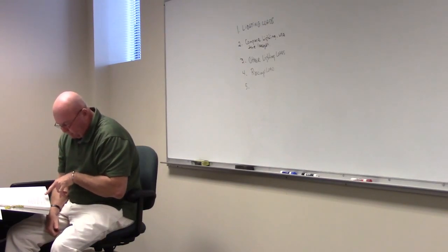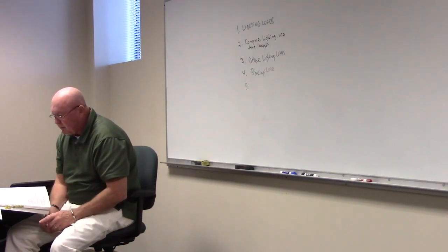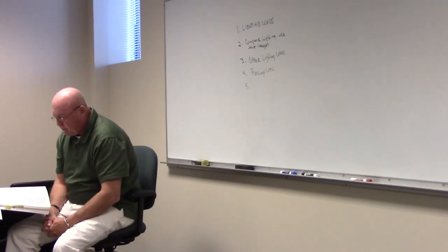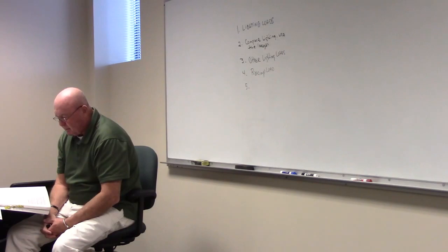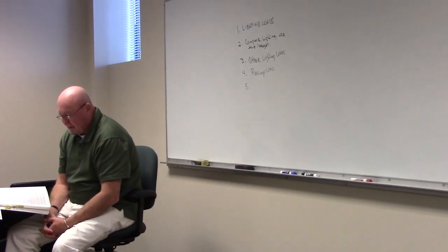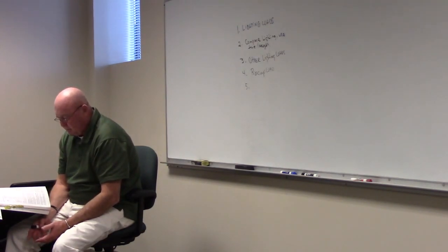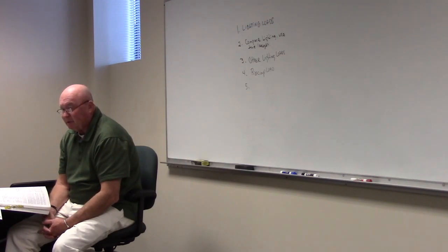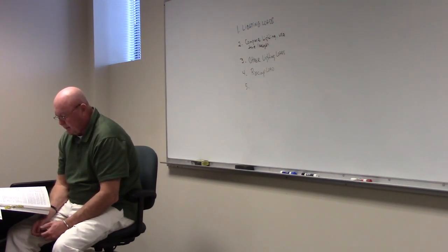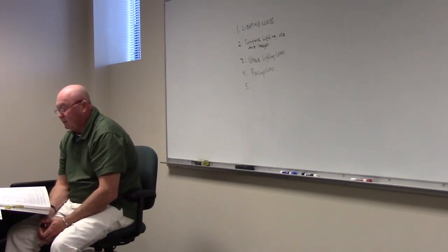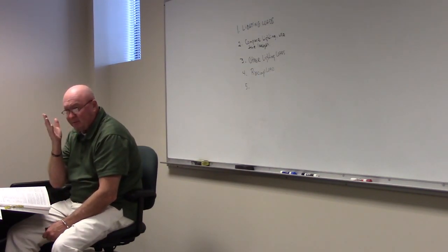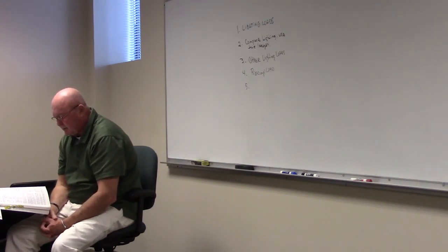If you look at 220.44, it talks about it. And then if you look at Table 220.42 up above there, lighting demand loads. Matter of fact, let's look at a warehouse. A warehouse says that for the first 12,500 what? 12,500 square foot? No. 12,500 what? Volt amps or watts. We're going to take it at how much percentage? 100%. And then everything over 12,500 in a warehouse, we're going to do 50%. Okay. 50%. Big thing.